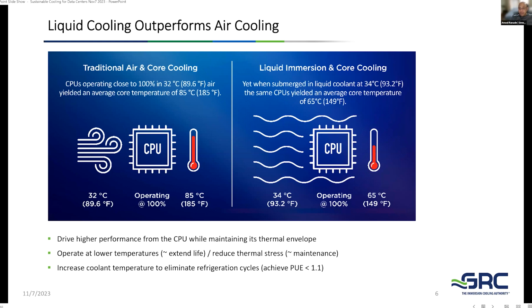And the third is, if I really want to take benefit of efficiency, if I am operating at 65 degrees or 85 degrees from a chip temperature, if I can take the coolant to a higher temperature like 50 degrees Celsius, do I really need a refrigeration cycle? That becomes a question. Today when we do air conditioning, the ambient temperature is higher than the temperature you want to maintain inside, and hence you need a refrigeration cycle. You need a refrigerant, you need a compressor, etc. If I am able to get a coolant at 50 degrees Celsius, and your ambient temperature in summer is, let's say, 45 degrees Celsius, I am hotter than the ambient, which means I can reject heat without a compressor.